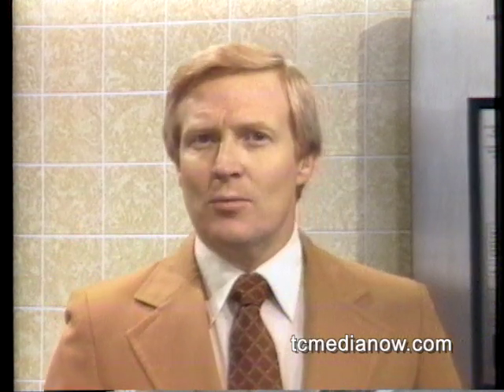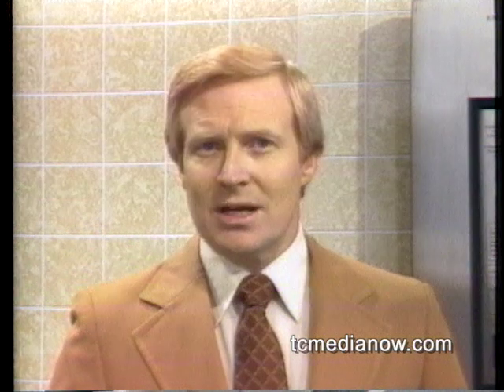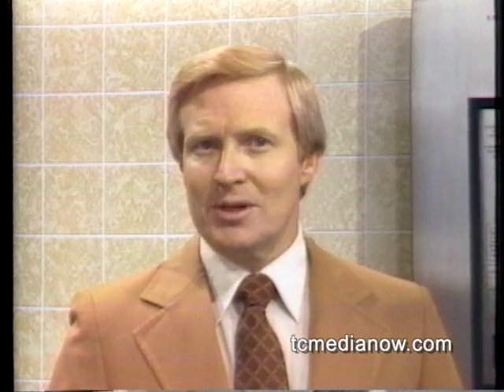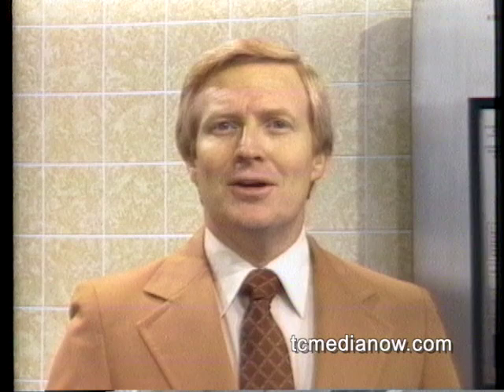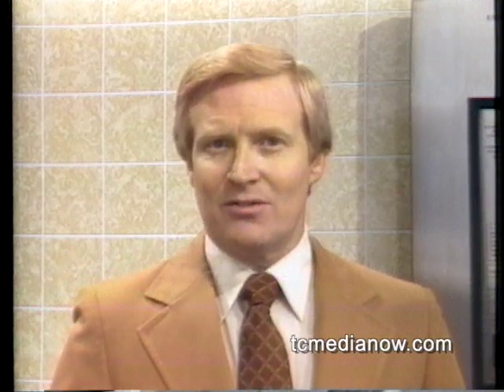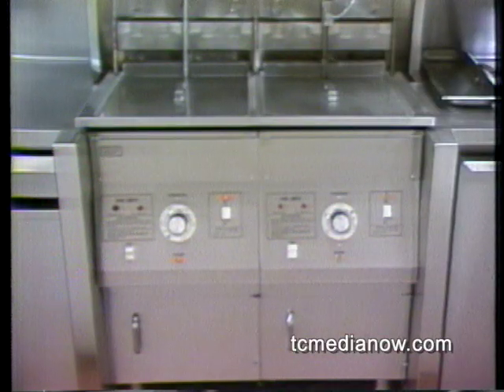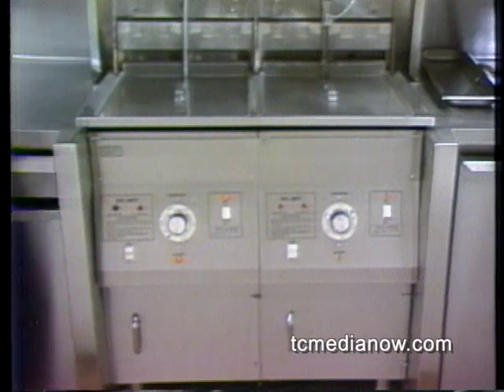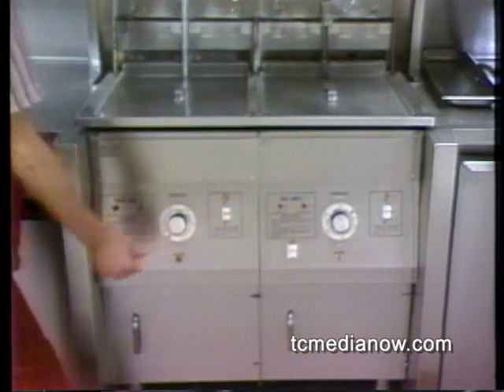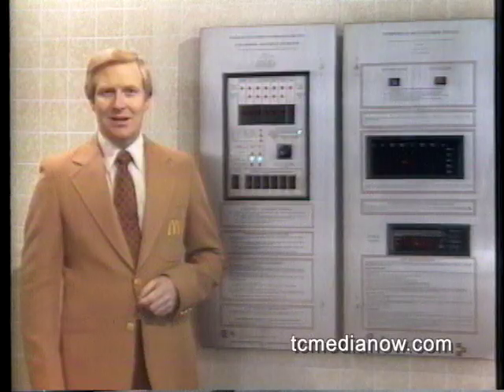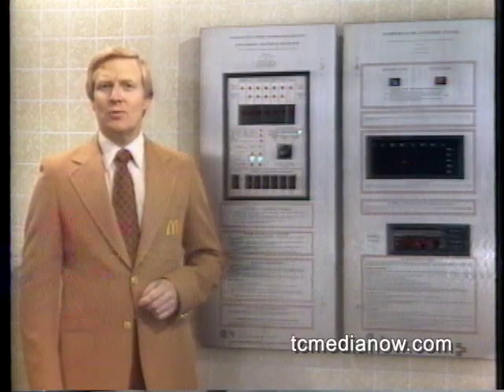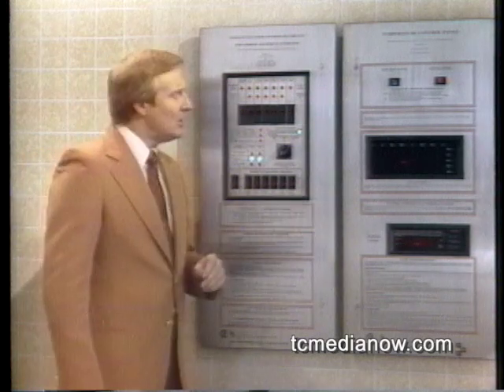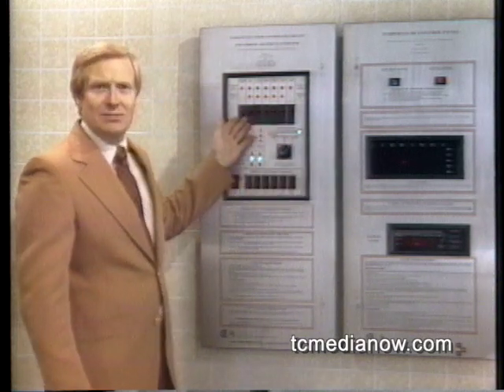The clock without thumb wheels does not automatically reset to the correct time of day after programming has been completed. Instead, the Restore Time button performs that function. Also on the clock without thumb wheels, the Filet Fryer override holds the entire store in daytime mode, not just the kitchen area. The Energy Interlock system is equipped with indicators that make finding and correcting trouble conditions easy. All of these indicators are explained in system instruction manuals.